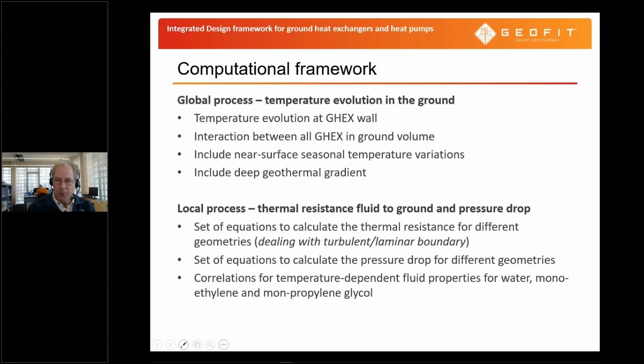On the other hand, if we do vertical boreholes, we also have to take into account that there may be a deep geothermal gradient where the deeper we go, the warmer it gets. It's usually between, let's say, 15 and 30 Kelvin per kilometer depth. On the other hand, we have a local process. This is the process in and around the heat exchanger itself, where we're dealing with the thermal resistance between the fluid and the ground, and also the pressure drop, which affects the pumping power.